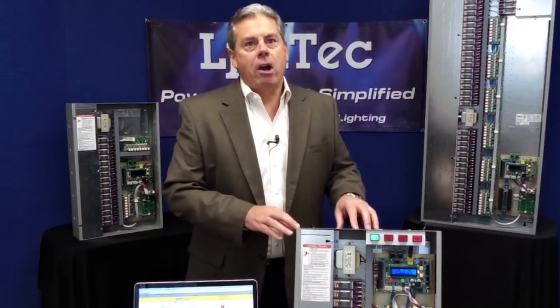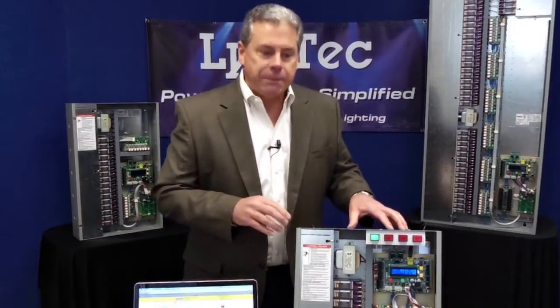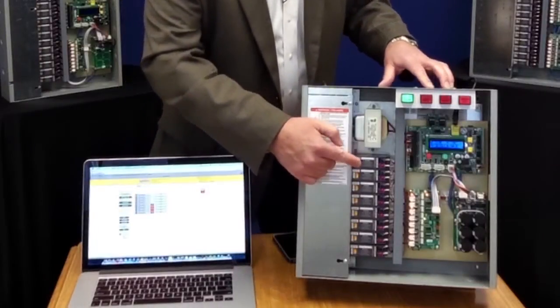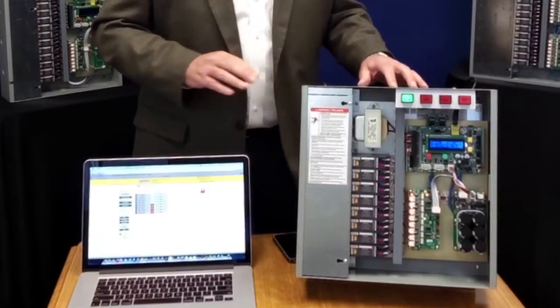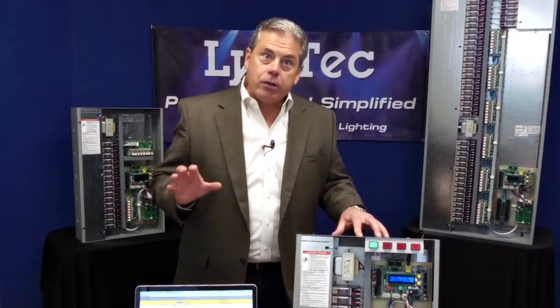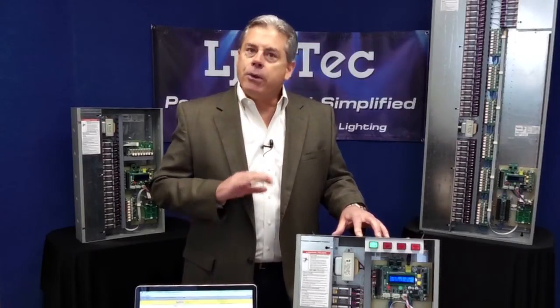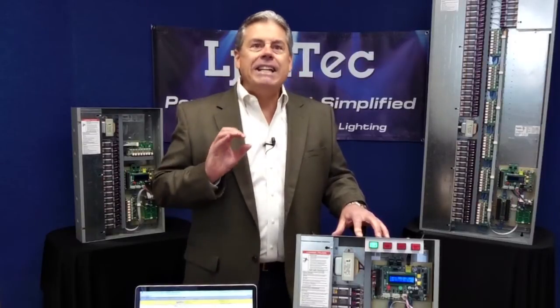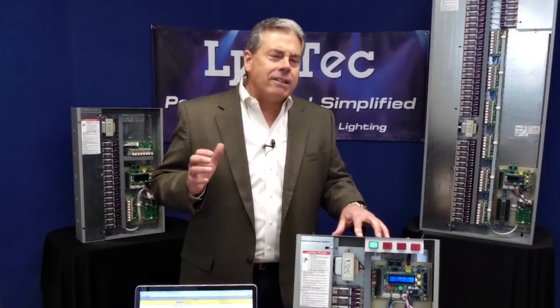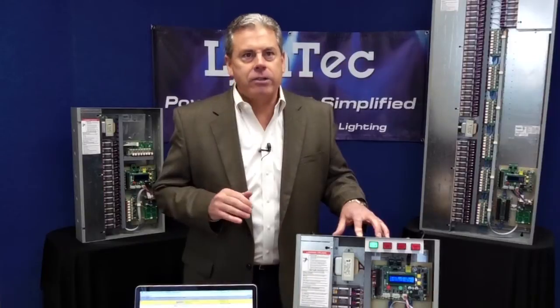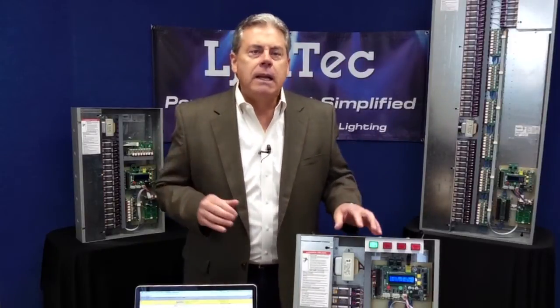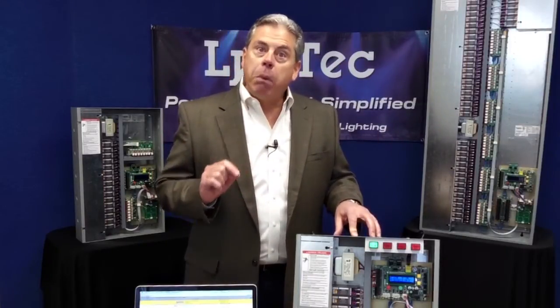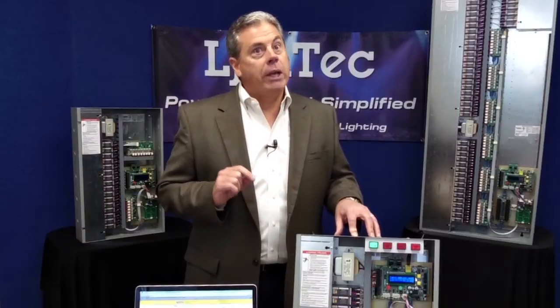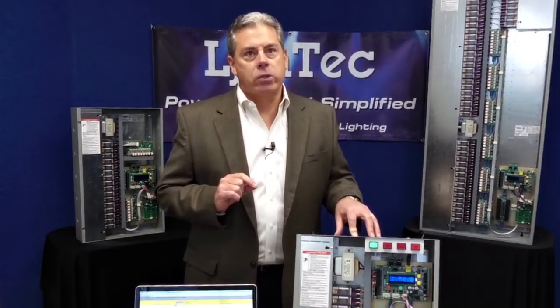So what does the RPCR control? The RPCR contains Panasonic latching relays. By having an electrician insert these in between your existing circuit breakers and the electrical equipment that you'd like to control, you can add on-off control to any device that you'd like. For example, lights, AV gear, video walls, video monitors, computers, individual outlets, etc. Panasonic relays come in one or two pole, 20 amp variations, so we can control 120 or 208 volt circuits.